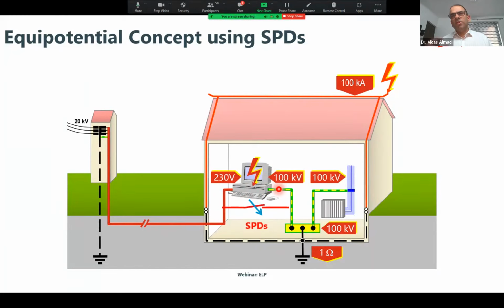Everybody knows about equipotential bonding, but let me tell you again. Like in case of lightning or in case of surge, the phenomenon that takes place is that on one side your potential becomes very high, on the other side the potential remains low. So when this potential difference is there, the current will flow from high potential to low potential. And this potential difference, if it is appearing across the device, it will break the insulation of the device and flow through the PCBs or like an arc. So in order to avoid the failure of this equipment, you need to bypass this current.